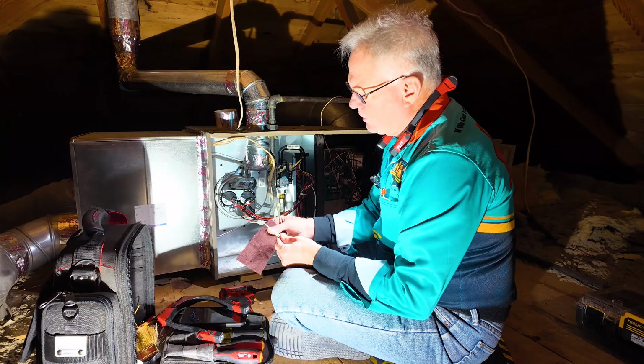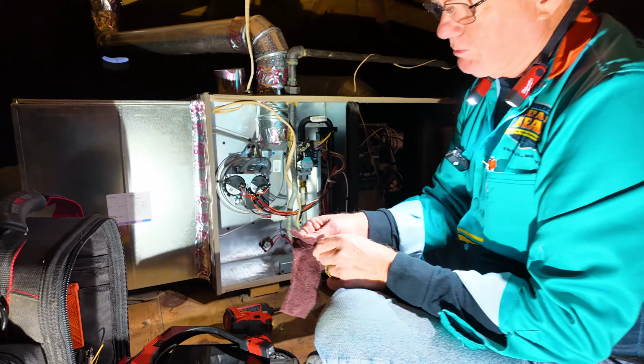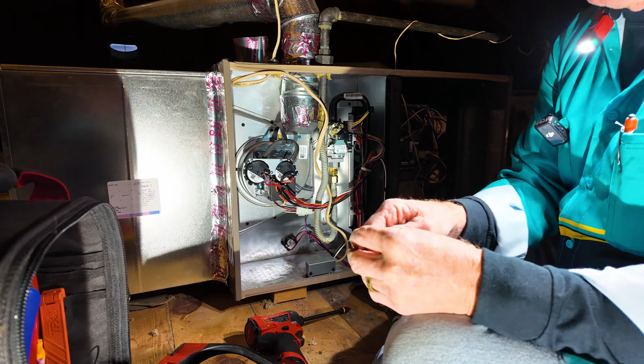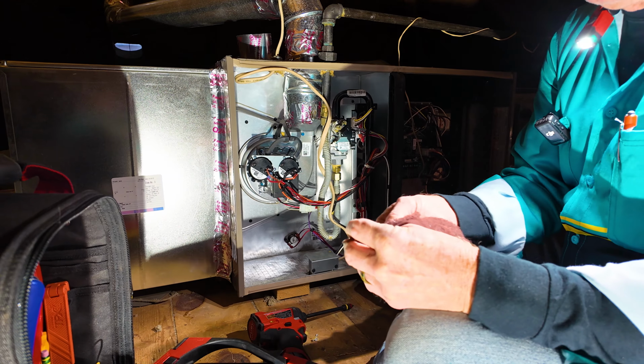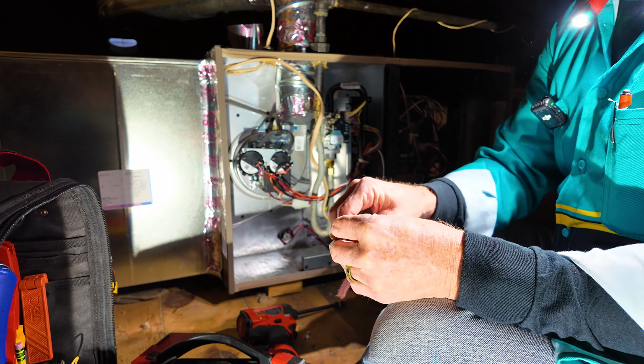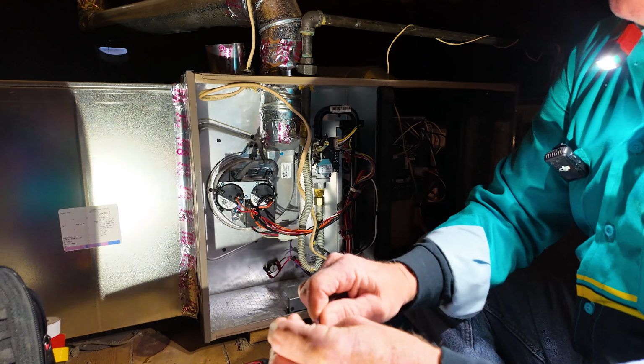So now it's here, and I'm going to use like a Scotch-Brite pad. It's just stainless steel. This isn't like a thermocouple or a thermopile that has a thin coating of bimetal or something on it that you could damage with sandpaper or anything rough. So I just use this to clean it off good with, like I said, a Scotch-Brite pad here. And I just clean it good because it's just stainless steel.